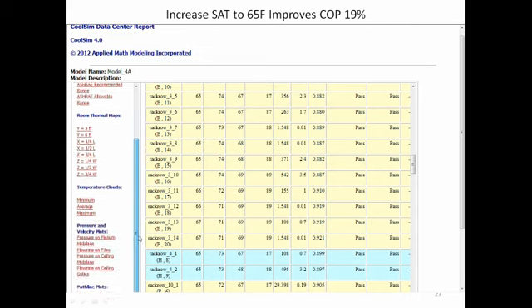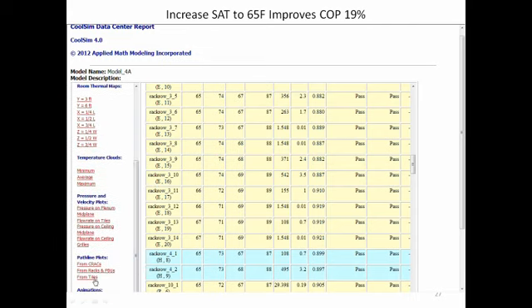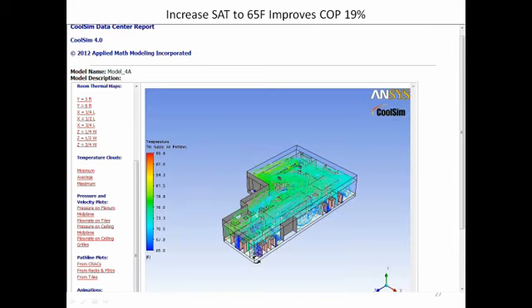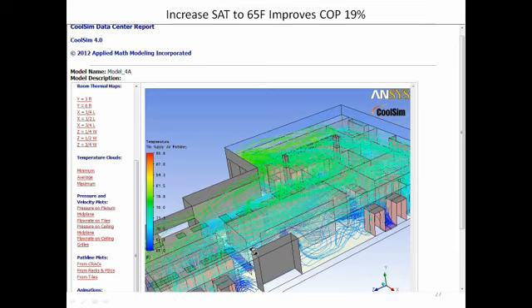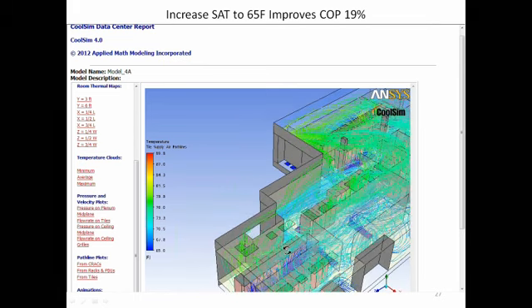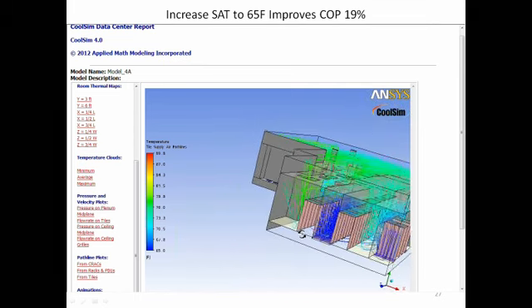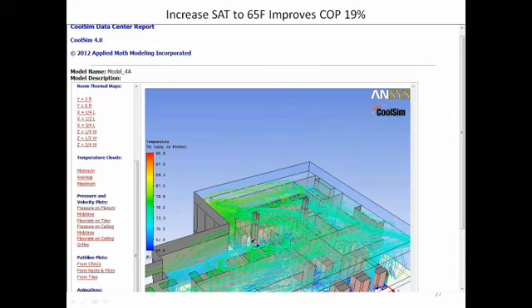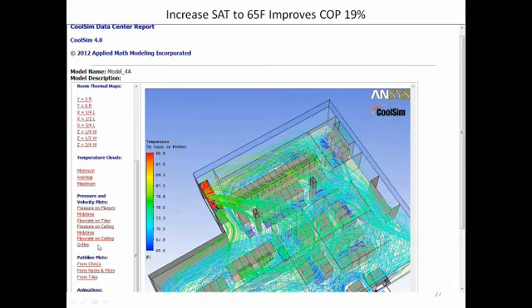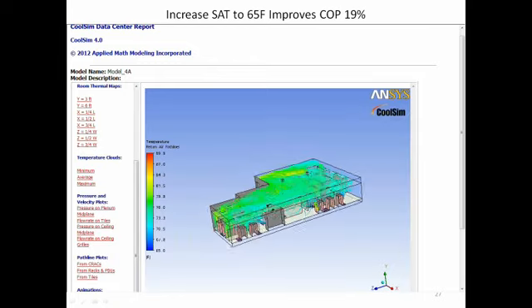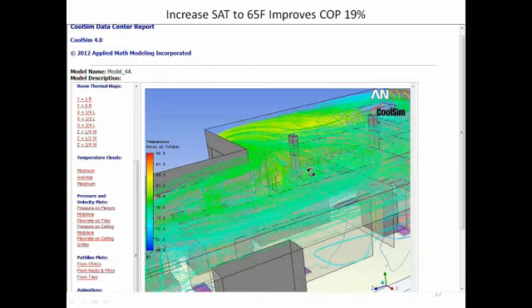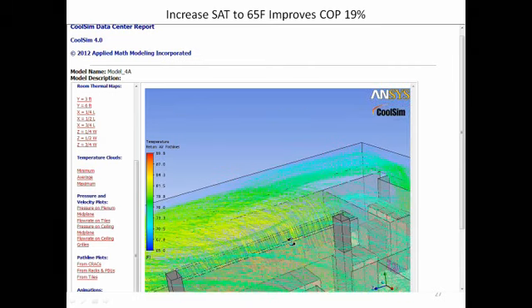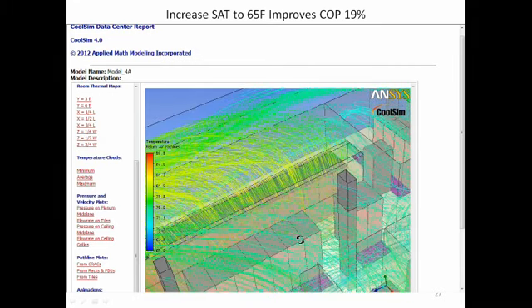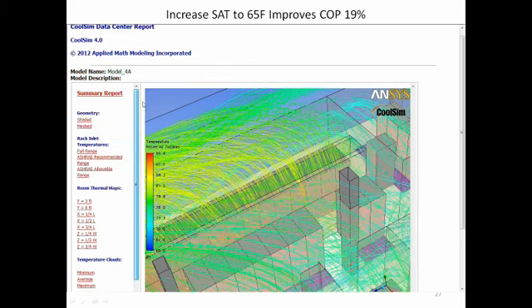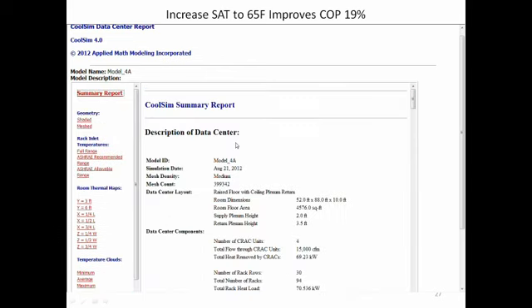This is the optimal case. You'll see here now that if we go back and we take a look at pathline plots again, things are even better behaved than they were. We've got the cold contained here, so it can't leak out of there. I've got good containment down that end of the room. I've got hot aisle containment up here. I can show you the hot being trapped. These get a little busy with a ceiling plenum return, but as you zoom in, you can see the hot coming straight up out. The hot temperature, if we take a look at the return temperature in our summary report, is in pretty good shape.